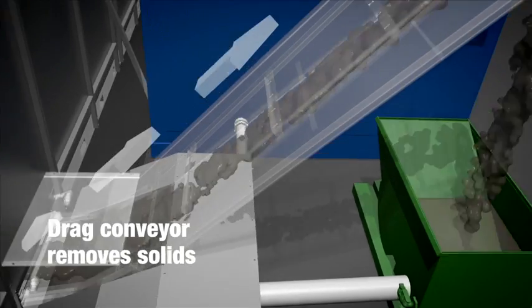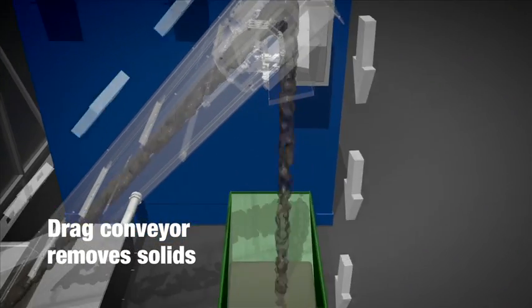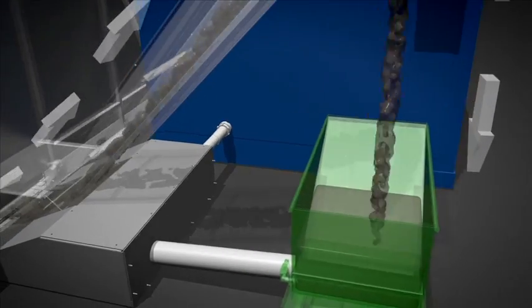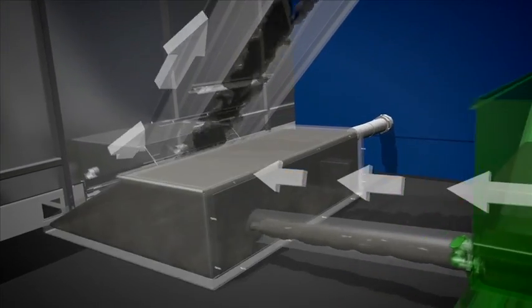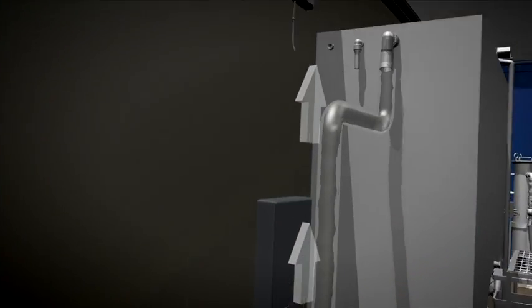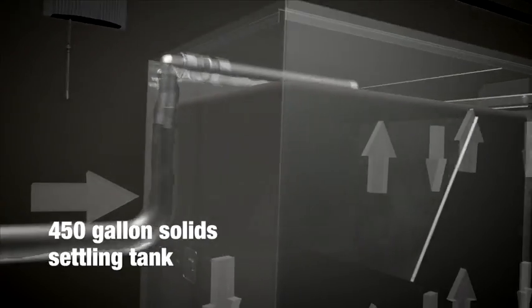The water filtration system begins when an automatic mud conveyor dumps mud into the portable hopper for proper disposal. Water then passes into a 450-gallon solid settling tank where a skimmer removes any oil and grease.